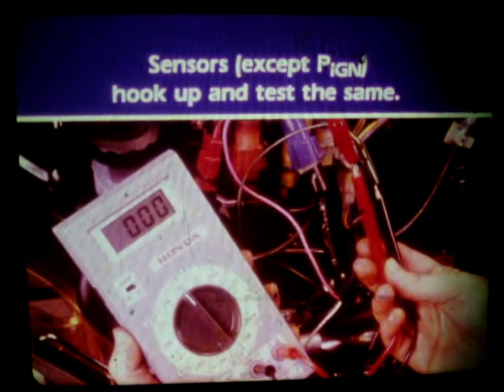All pressure sensors are tested exactly the same way. The only exception is the PIGN sensor. The PIGN has reverse polarity and is hooked up for testing in the opposite manner. See the troubleshooting section of the shop manual for details.